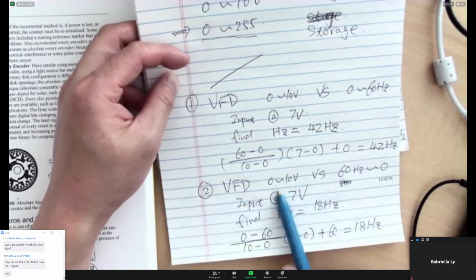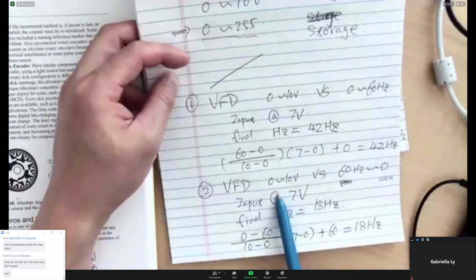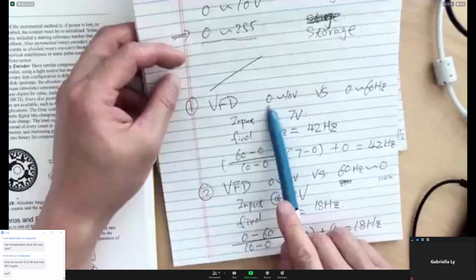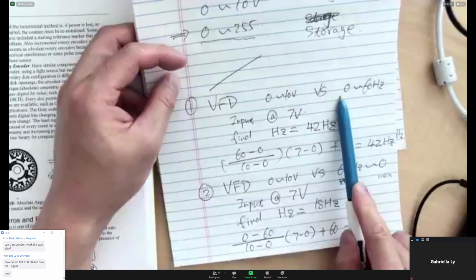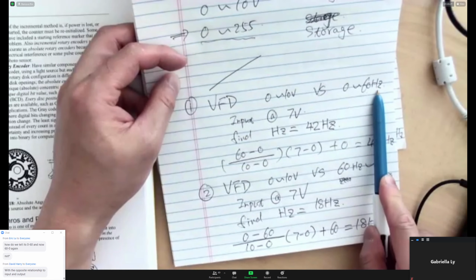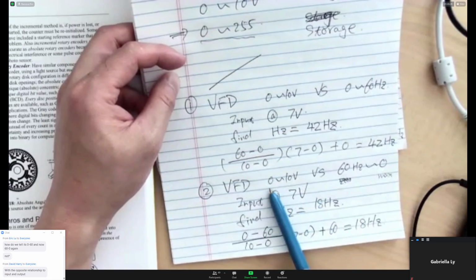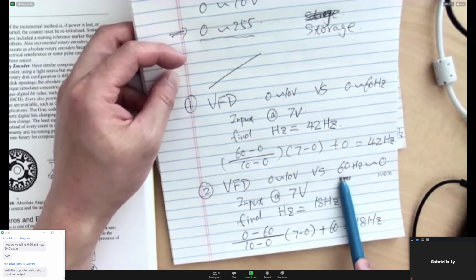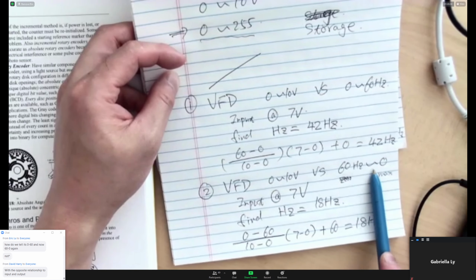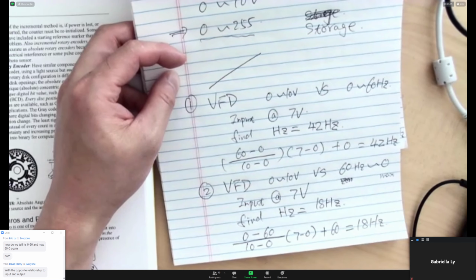They will tell you. They will tell you if for 0 to 10 volts the output is 0 to 60 hertz, or if 0 to 10 volts gives output 60 hertz to 0, an opposite relationship between the input and the output.